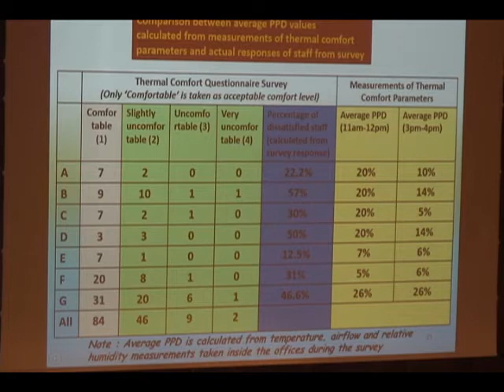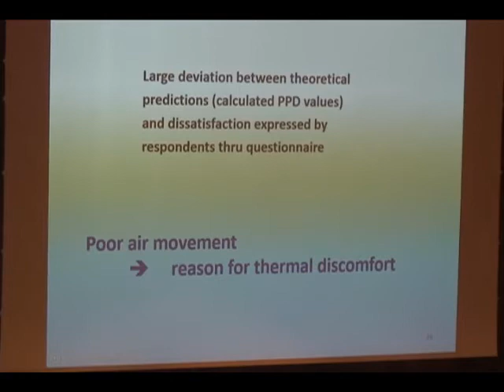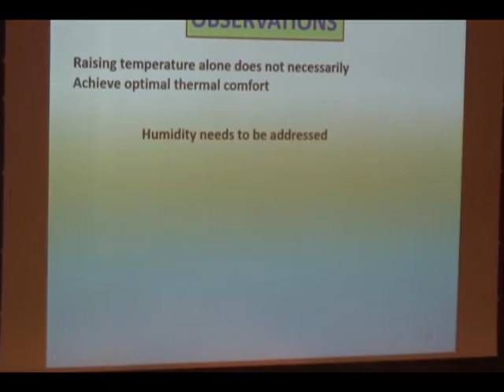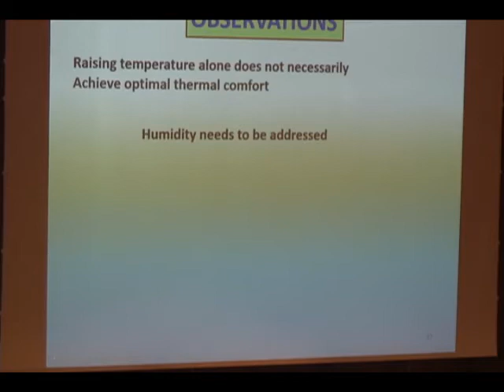That's another interesting observation, and there could be a couple of reasons for that, but that's not what I was focusing on at this point. Just to make the point that elevated space temperature - only raising the temperature, not doing anything else - did not seem to be a very viable or good solution to solve the problem. Air movement, as I just showed you through that table of measurements, was indeed the main reason for thermal discomfort. The humidity levels were also not exactly what we would like to achieve, partly because of the oversized coil part I discussed, and also because the air movement was not quite what would have helped us achieve thermal comfort.